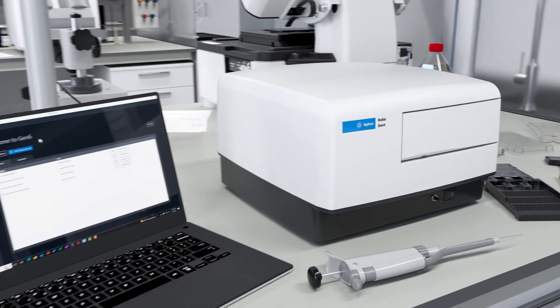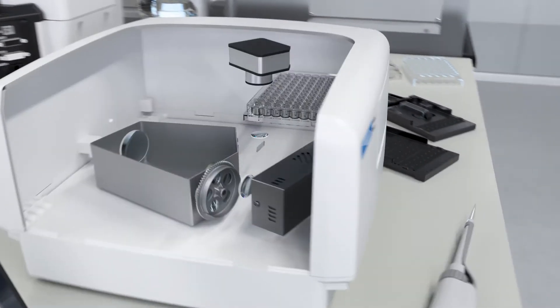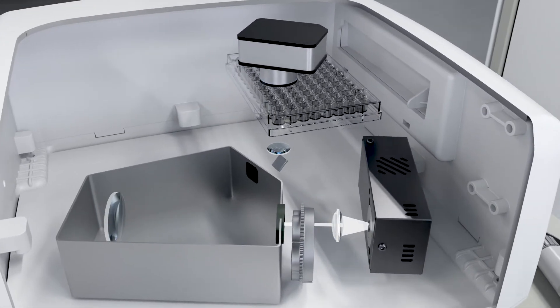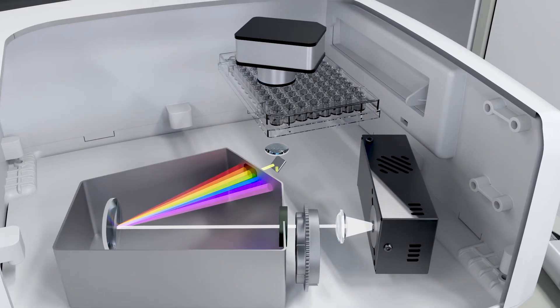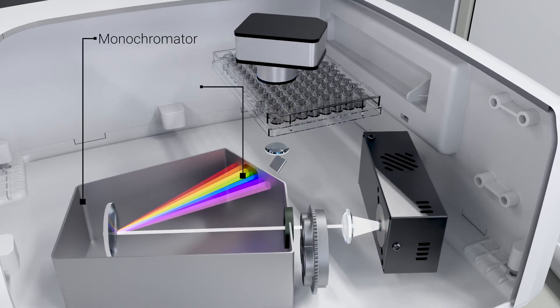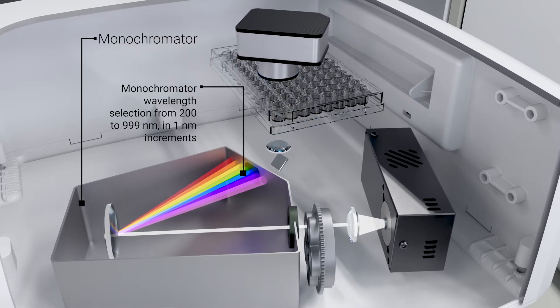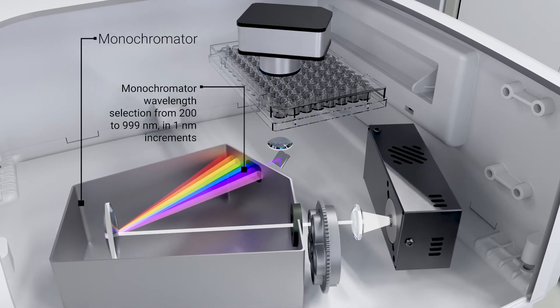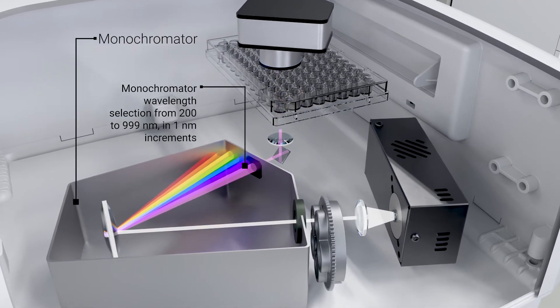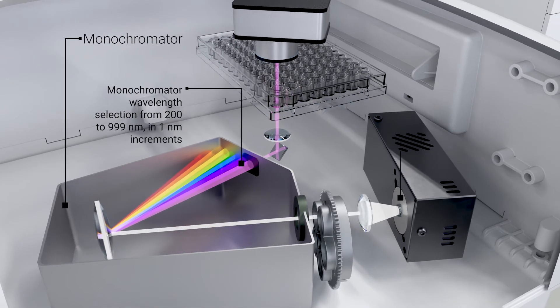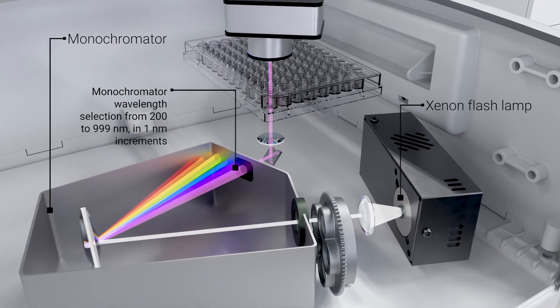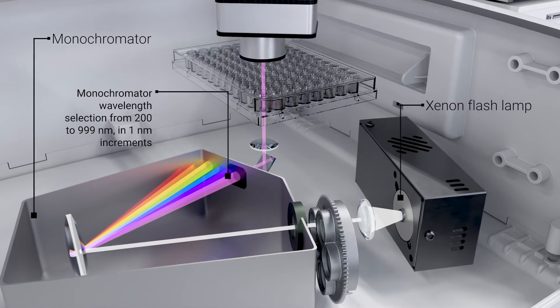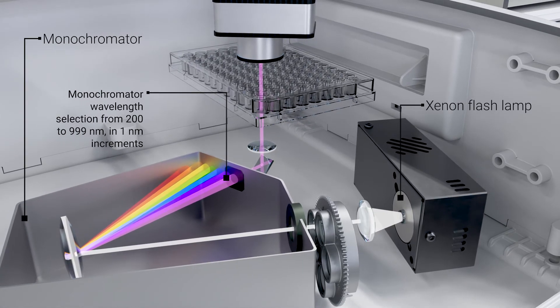Epic's monochromator-based absorbance detection features wide wavelength selection in 1 nm increments. For assays requiring one or more reference wavelengths for proper data analysis, multiple wavelength reads can be programmed in Gen 6. The high-quality Xenon flash lamp offers a wide wavelength range and a light source that's rated to last, requiring infrequent replacement.